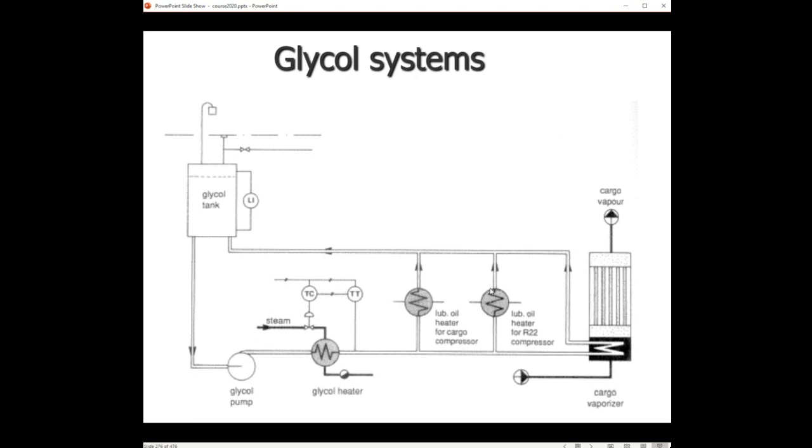But okay, when your compressor is stopped, you can make sure that your lub oil is kept at plus 40 degrees, so that condensation of the cargo is avoided. When your compressor is running, then you can use this 40 degrees as a cooling medium, because you will avoid that your compressor is reaching too high temperatures. So in both cases, it will work. And of course, this is only an example of some applications, some consumers of this glycol system. This glycol system can be connected to a lot more applications, but just for simplification, I only mentioned a few.